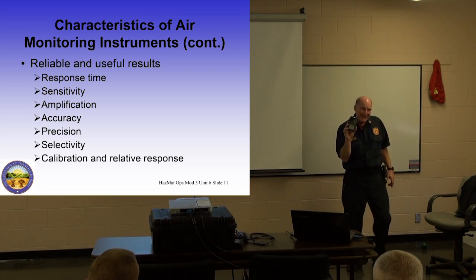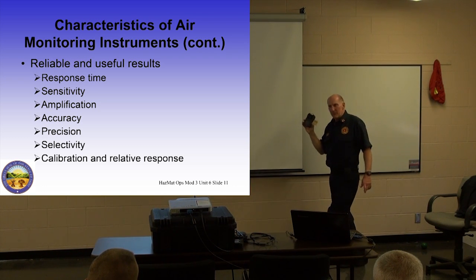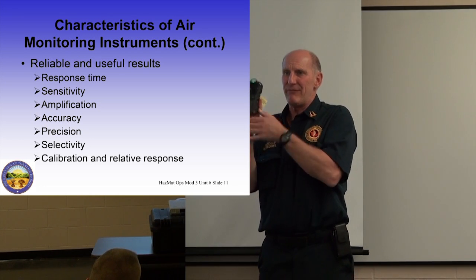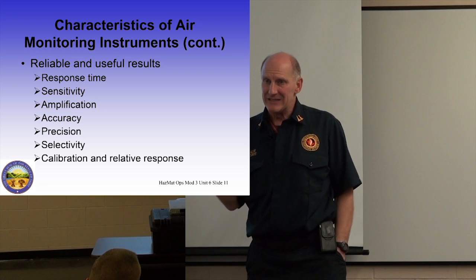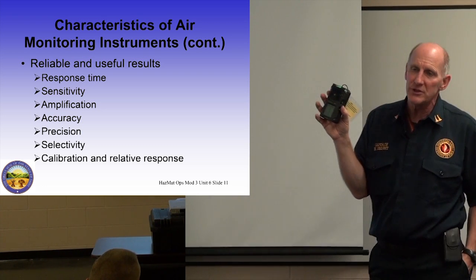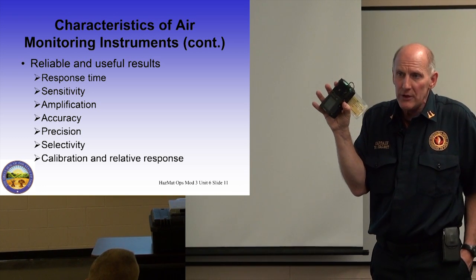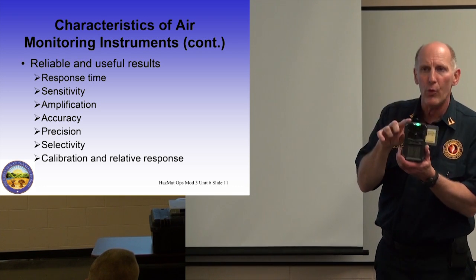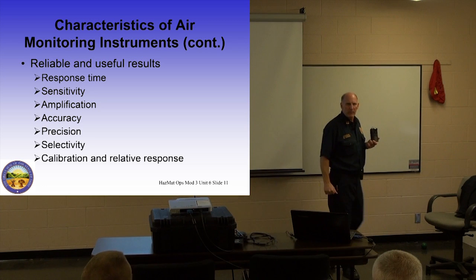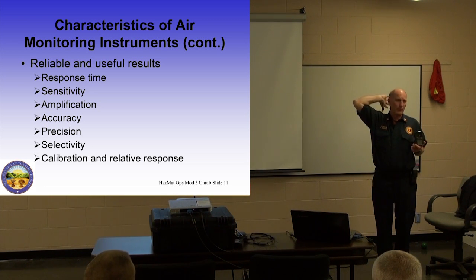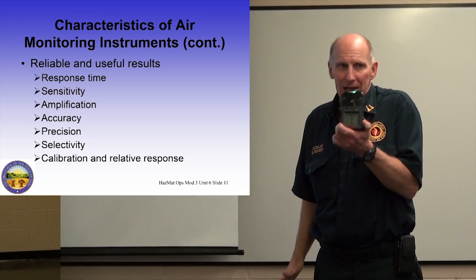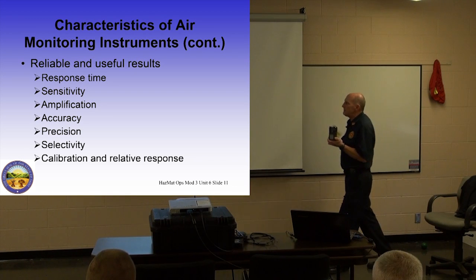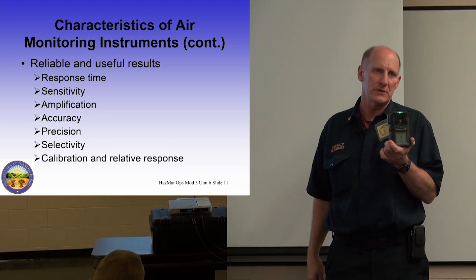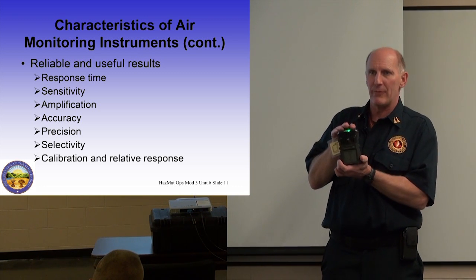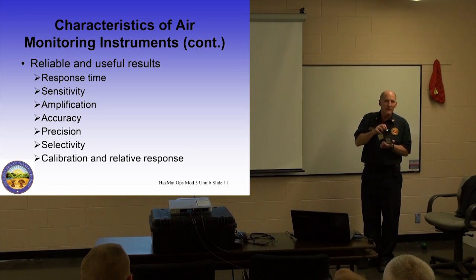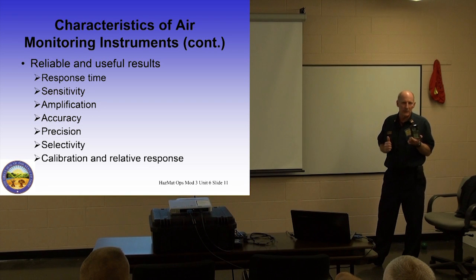Precision. Is it exact in what it's measuring? The next big problem with this is realizing that this meter does not know what it's smelling. It does not know the difference between carbon monoxide or hydrogen cyanide or hydrogen sulfide. There are chemicals that will fool these sensors. So when I get a reading of 3 on the carbon monoxide monitor, I can't stand up and say, oh, there's carbon monoxide in this room, because it's not precise. It may not be exactly accurate. It may not be precise. There could be another chemical in this room that's fooling this sensor. Once again, the more I know about these, the more I can trust them. The more I think they're telling me information that they're really not telling me, I can't trust them. I'm liable to get myself into a dangerous situation.